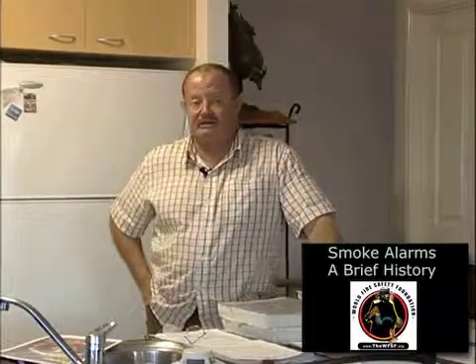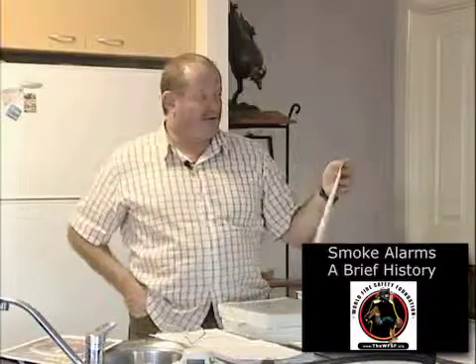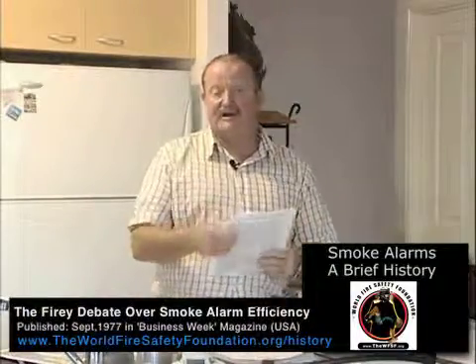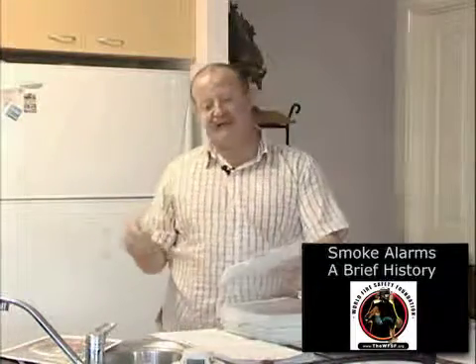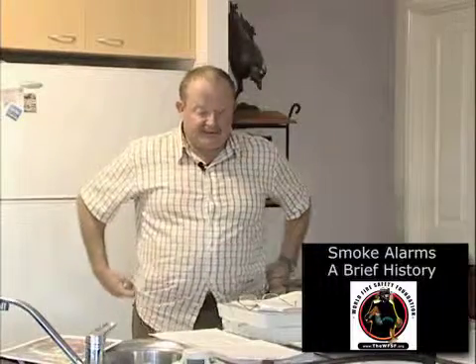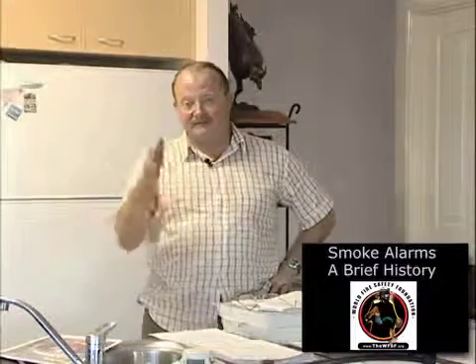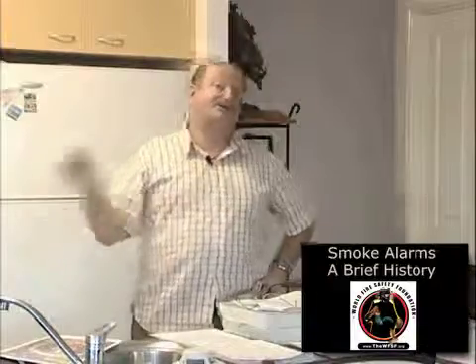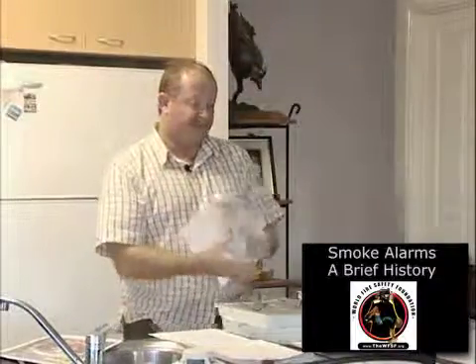He sent this out in 1976, and the following year, 1977, Business Week magazine published an article called 'The Fiery Debate Over Smoke Alarm Efficiency.' In it, Don Steele — regarded as the father of smoke alarms — said that he and his colleagues went into a room and found that no matter what sort of fire was burning, when smoke levels got to 4%, everyone was heading for the door. They found back then in 1977 that the human body cannot handle more than 4% smoke in a room. The industry was arguing that Underwriters Laboratories should keep the maximum smoke level that detectors must detect at no more than 4% — or at most 7% — arguing that if a smoke alarm doesn't go off at less than 7%, it should fail.